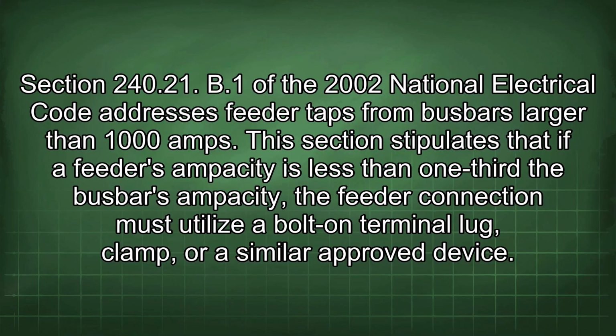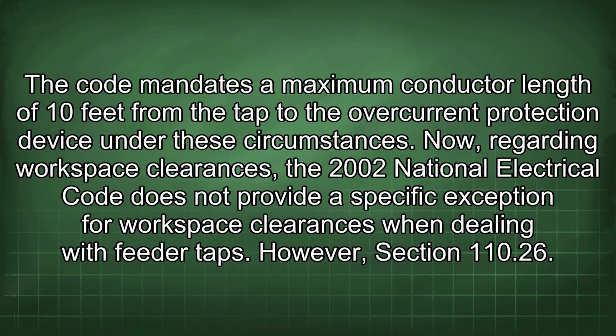240.21.B.1 of the 2002 National Electrical Code addresses feeder taps from busbars larger than 1000 amps. This section stipulates that if a feeder's ampacity is less than 1/3 the busbar's ampacity, the feeder connection must utilize a bolt-on terminal lug, clamp, or a similar approved device.